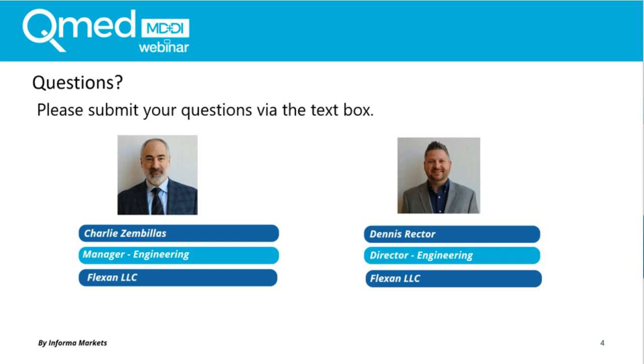Our next question asks, are there any fillers or additives that you can add to silicone to change its mechanical properties? Well, barium sulfate changes the mechanical properties a little bit, however, is generally used to be radio-opaque. If a customer approaches us with other fillers or additives that they'd like to experiment with, we may be able to work with them and, in conjunction with our manufacturers, come up with whether it's an appropriate blend that may not hurt the curing mechanism or the properties. All right, thank you, Charlie.